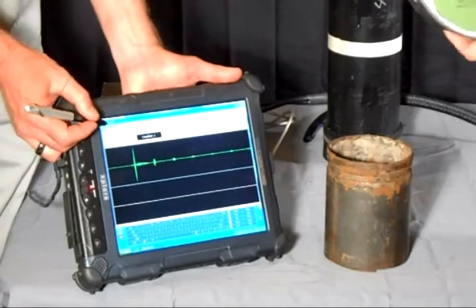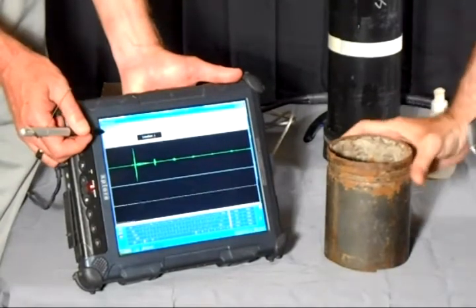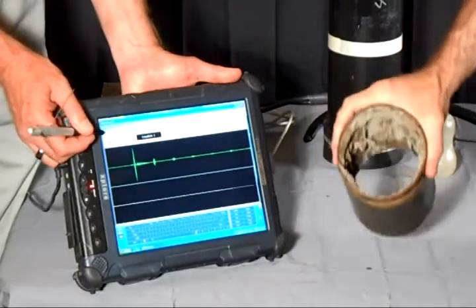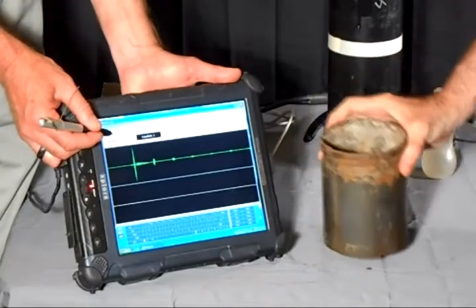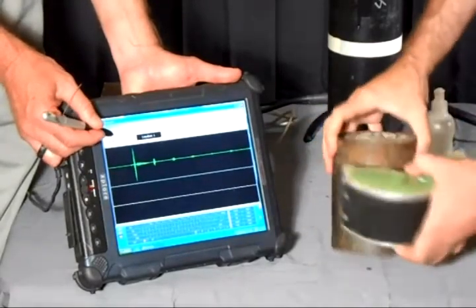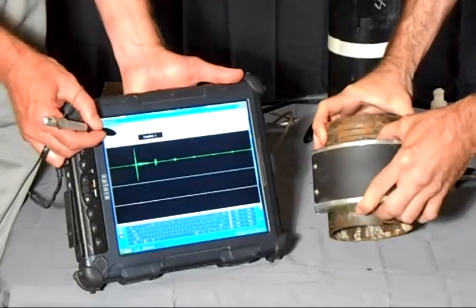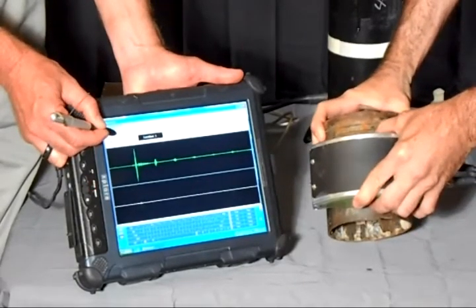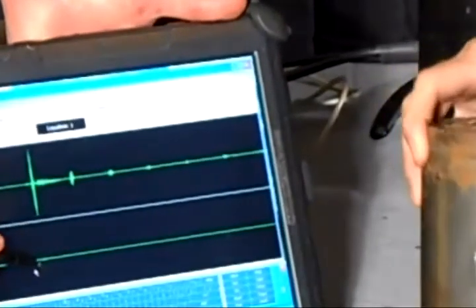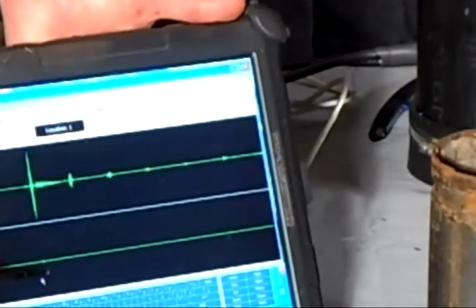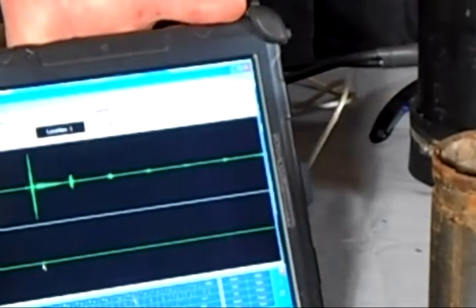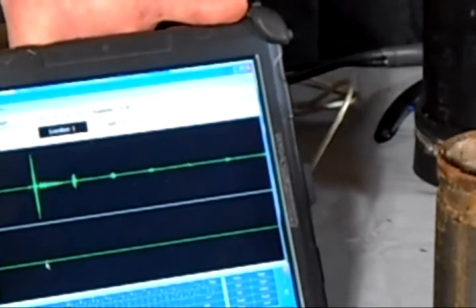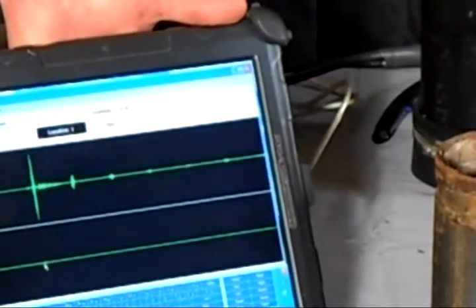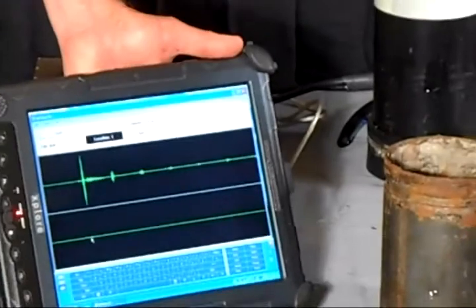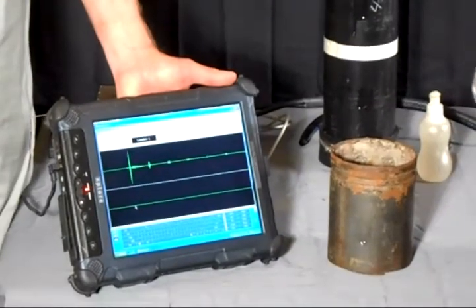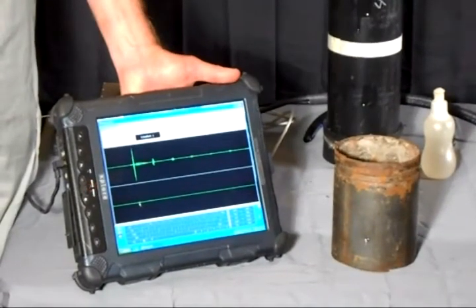So now we're going to run our scan on the corroded piece of pipe. By the way, this corrosion is one of many different types of things that we can find with this technology, but it's just for an example here today. As you can see from this, there's a little teeny blip where the first pulse of sound energy is. The rest of it is a flat line. What's happening there is the corrosion inside of this pipe is absorbing all of our sound energy. It gives us a very clear indication that there is some severe corrosion present inside that pipe.